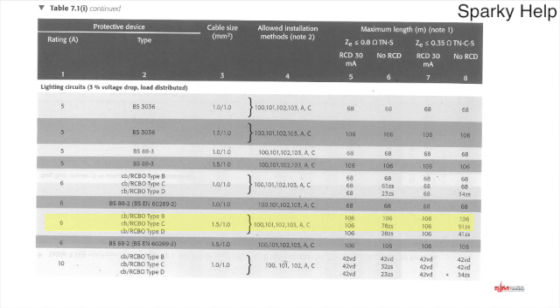So 101, 102, 103, A and C. So this is clip direct, this is on the side of a joist, it's touching plasterboard. So providing you're installing it in that way, then we can look straight across to the other columns, and at the very top you can see the type of earthing system. So if it is a TN-S or a TN-C-S, with or without an RCD, we can look across there. So if we look up here at a TN-S at 0.8, and this is a maximum of 0.8, that's what you've got with a 30 milliamp RCD.